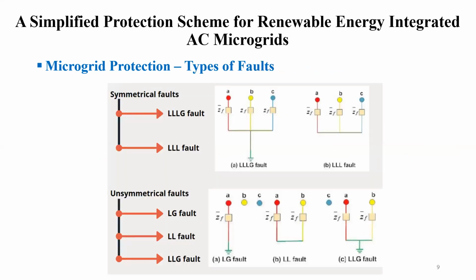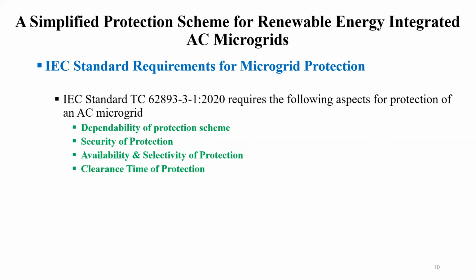Generally, discussing types of faults, there are symmetrical and unsymmetrical faults. The symmetrical faults are the line to line to line to ground, or LLLG fault, and the line to line to line fault. In unsymmetrical faults, we have the line to ground fault, line to line fault, and line to line to ground fault. These are the types of faults we have considered in our results and in this paper. When we develop a microgrid protection scheme, we have to consider the IEC standard TC 62893-3-1, which was revised in 2020.